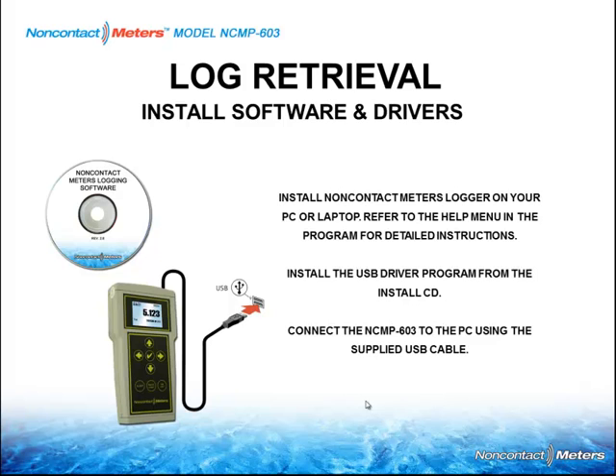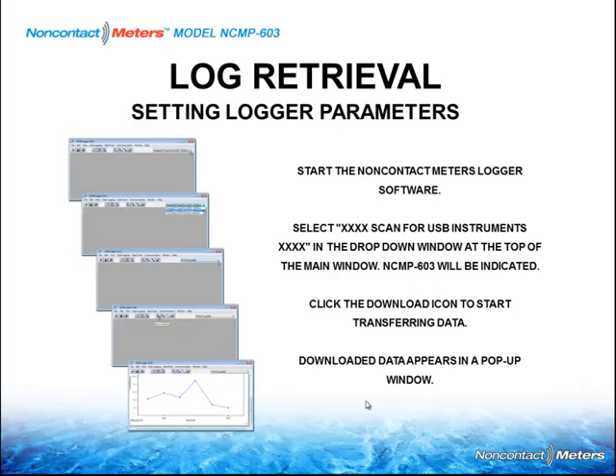We will provide you with a piece of software and a USB cable that you plug into your laptop or PC to say hello to this meter. And basically, to work the logger, when you use the software and plug everything in, it'll go through a discovery process, and you'll select the scan mode for the USB instruments, and then the main window will detect this particular meter. Click the download icon to start the transfer of data, and then the downloaded data will appear in a pop-up window, as you can see down over here. What you're going to get is a spreadsheet and a graph. And also you can export this data from this software program to Excel should you like to do that as well.